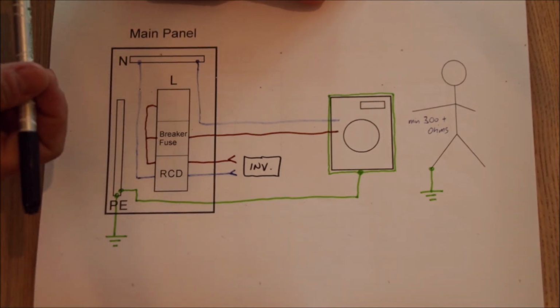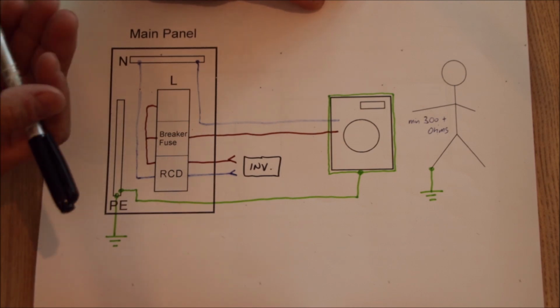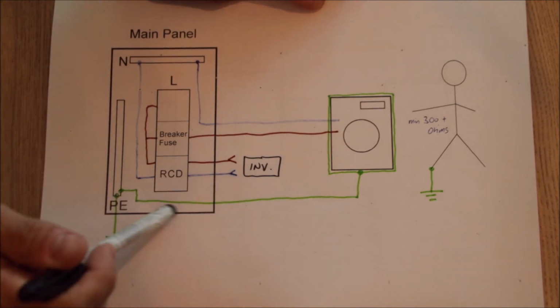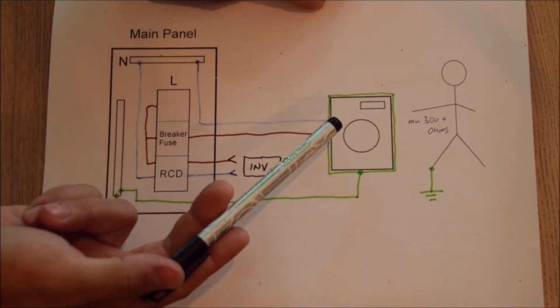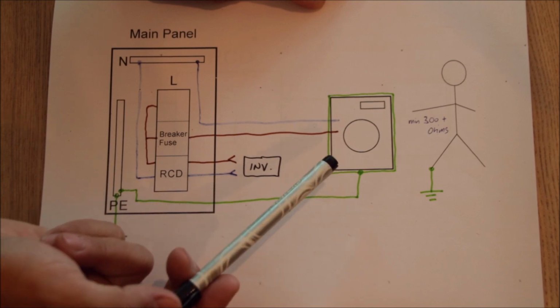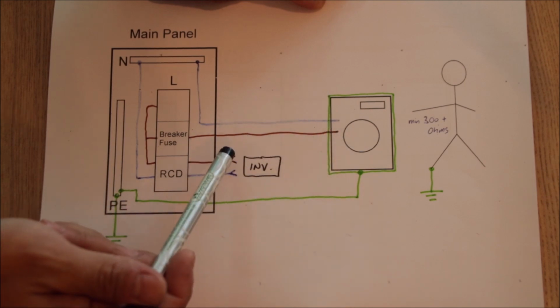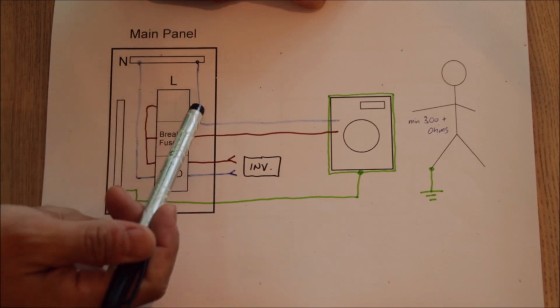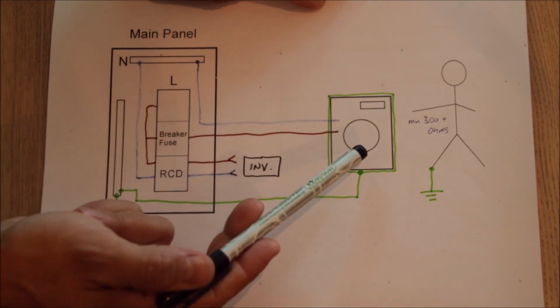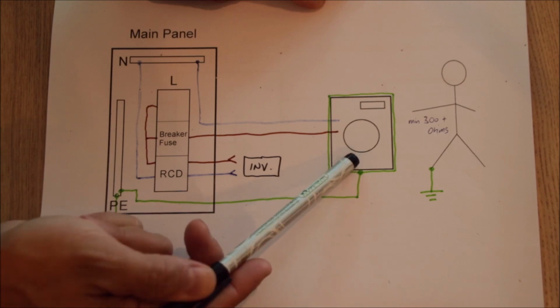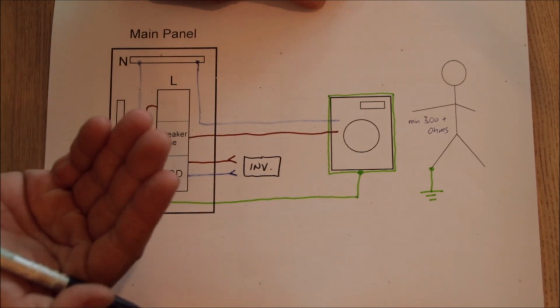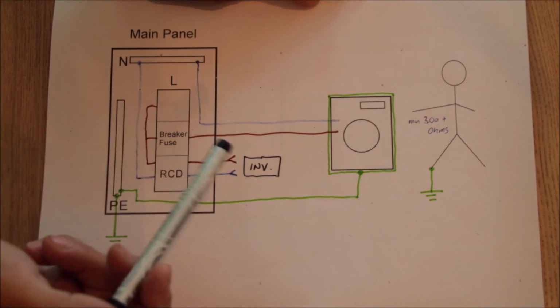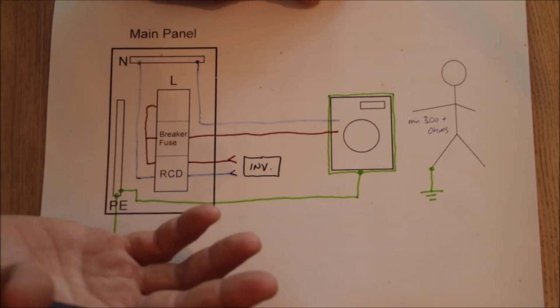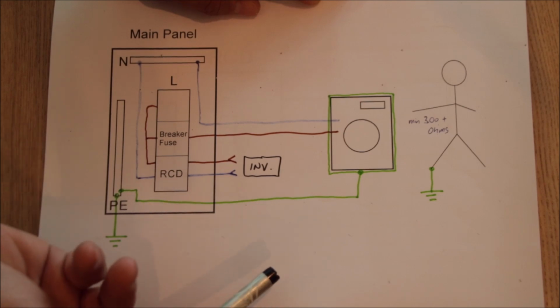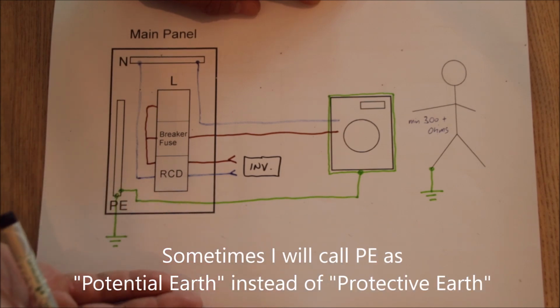An electrical system in regard to earthing always has two separated parts. It has the normal electrical circuit, which is the hot wire and the neutral wire, and currents will flow on those active wires from the source to the appliance and then back again. And then the second part of the electrical installation is the protective installation, the protective shell around the appliances. That's the PE system, the potential earth.